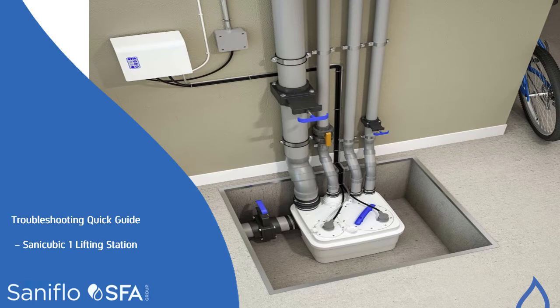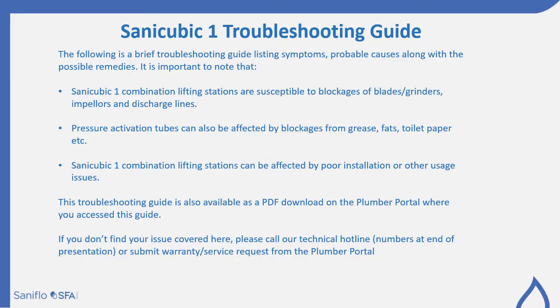This is a troubleshooting quick guide covering the Sanicubic 1 lifting station. The troubleshooting guide will provide some symptoms and possible causes along with the remedies that we might be able to suggest to you. It is important to note that the Sanicubic 1 lifting station is susceptible to blockages of the blades and the grinder assembly, the impellers and the discharge lines.